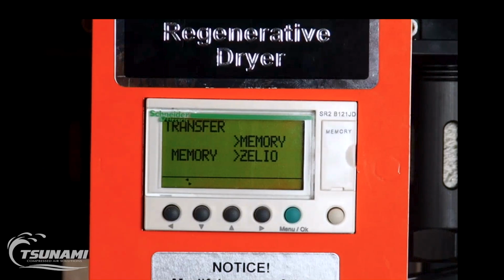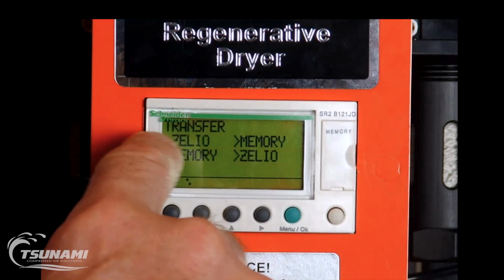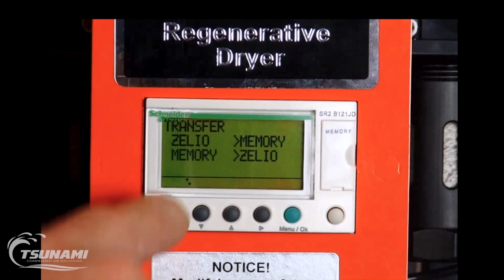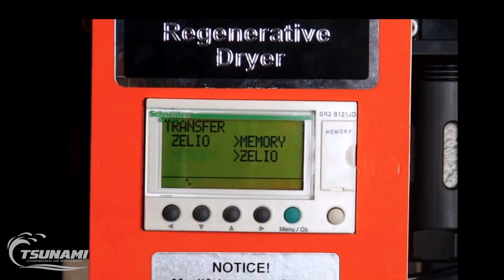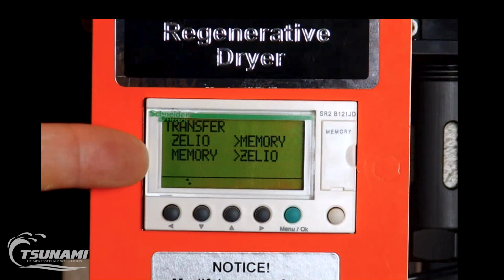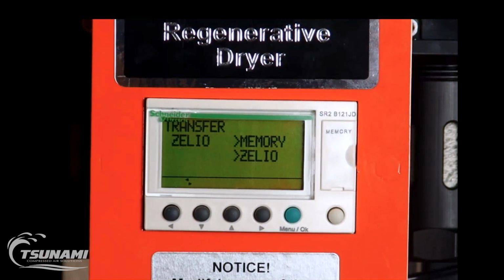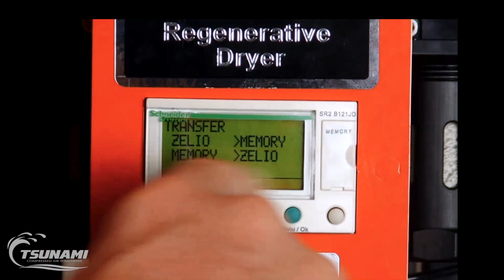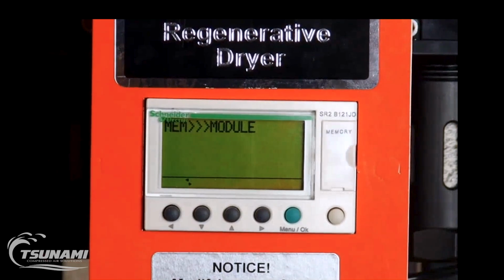Now here it's important to understand, you can't upload a program to that memory stick. We don't recommend that. If you do that, you'll be sending this back to us for us to reprogram the dongle. So what you want to do is you don't want to leave Zelio to memory. You want to hit the down arrow and have memory to Zelio. This is Zelio, the PLC model. So we want to go memory to Zelio and hit OK.